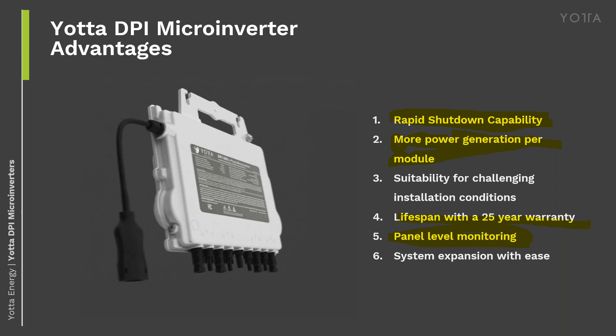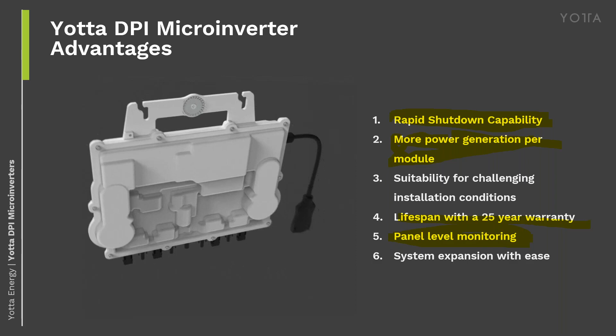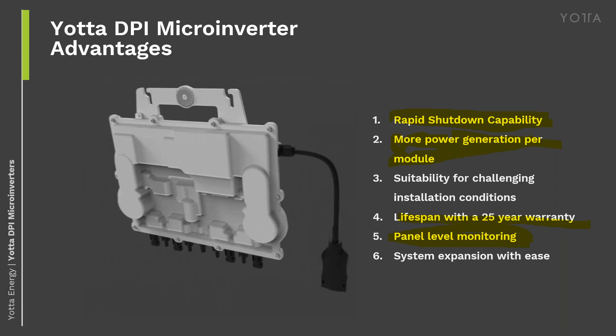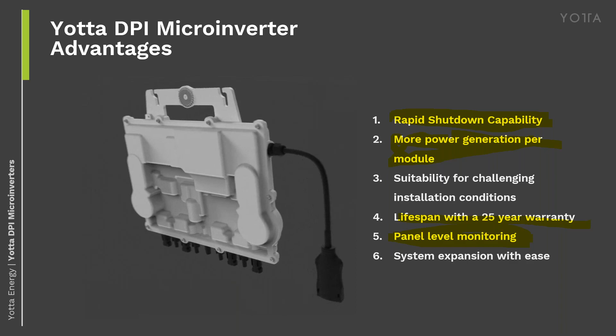But what was nice about that was the system was able to demonstrate to us that the module was actually the culprit in this particular case, because the other modules were producing somewhere in the 36 volt range, and this particular module was only producing 24 volts. That indicated to me and to him that a diode had been flipped, so the module was in fact the problem. He went out to the site with a replacement module. He knew exactly where the module was because of the mapping, and was able to fix the problem within minutes and not hours. Again, it's another one of those time savers, because you're able to identify the problem remotely, bring the right equipment to the site, go to the exact location, and fix the problem.